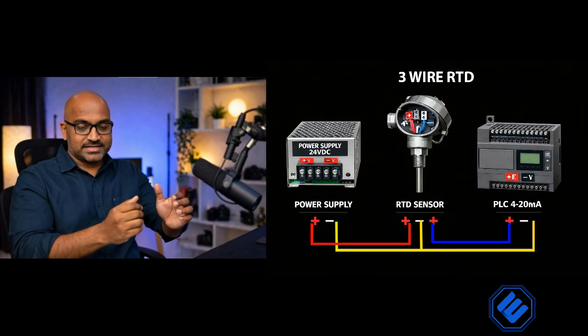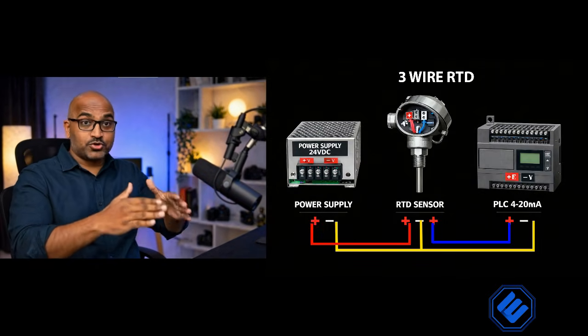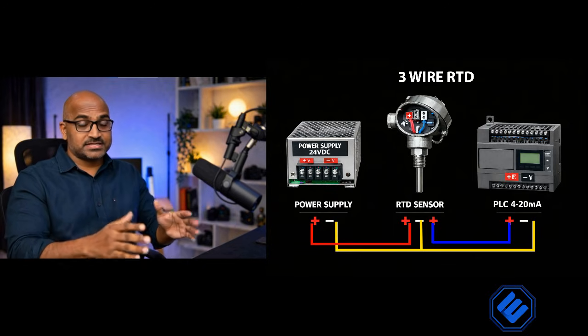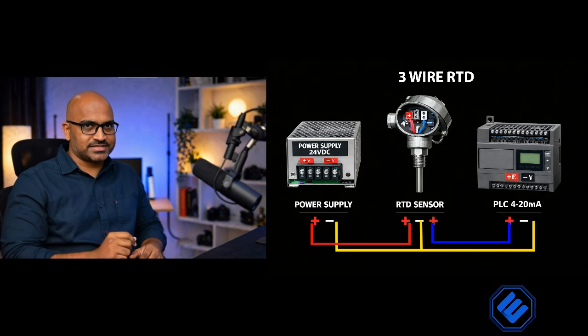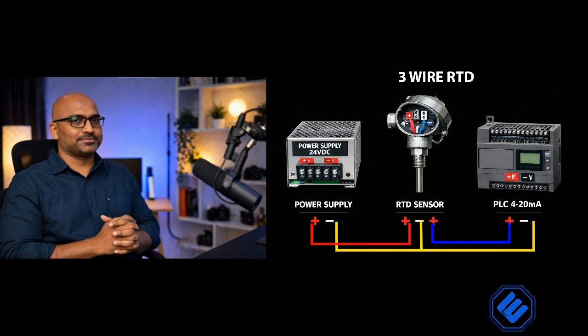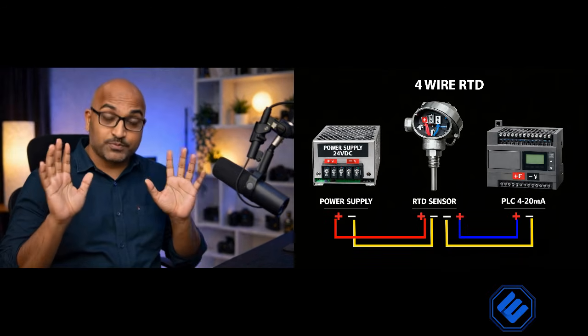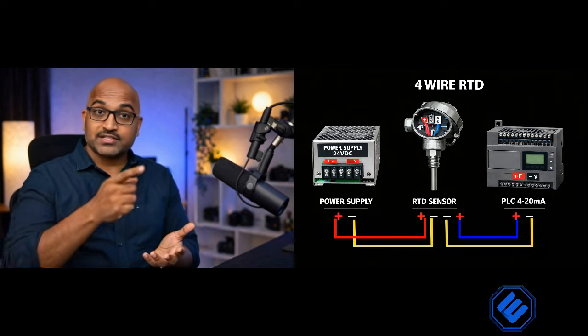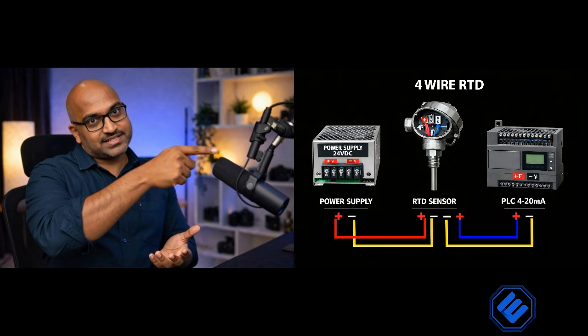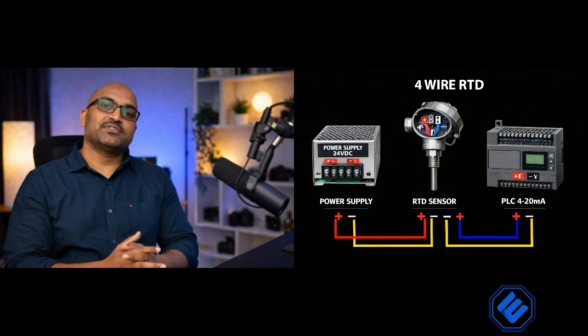3-wire RTDs are the most common. They add a third wire to compensate for lead resistance. Great balance of cost and accuracy. This is the industrial workhorse. 4-wire RTD, the most accurate. 2 wires for power to the sensor, and 2 wires to measure voltage directly across it. Completely eliminates lead resistance error. Best for labs, calibration, and critical processes.